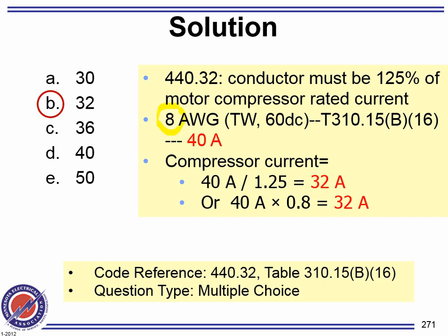Why did they go to, well, here, look how this changed. What if I told you guys this is a THHN? Which column would you go to and why? 75. Why not 90? We're not derating. Otherwise, you would have gone to 90. So what would number 8 give you at 75? 50. Everybody 50? Yeah. And then if you multiply 50 by 0.8, that'll get you 40. Am I making sense, guys?